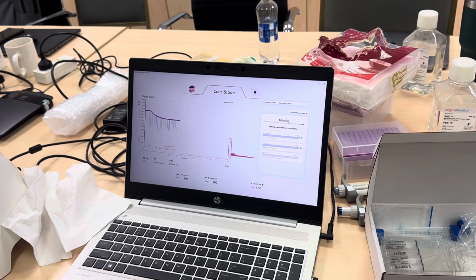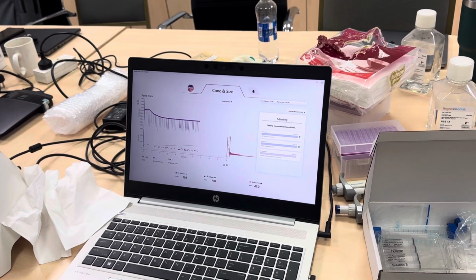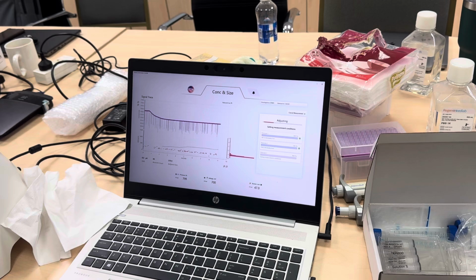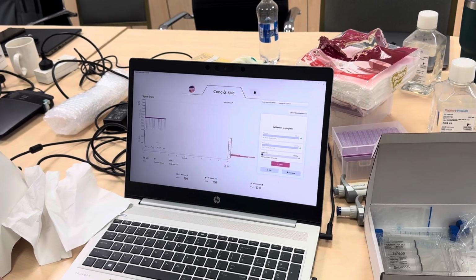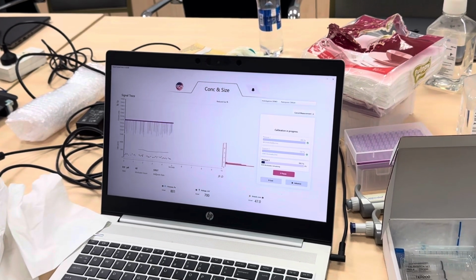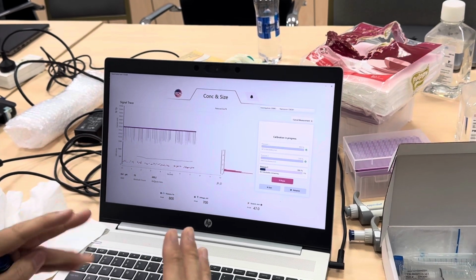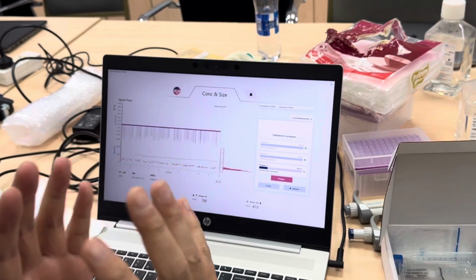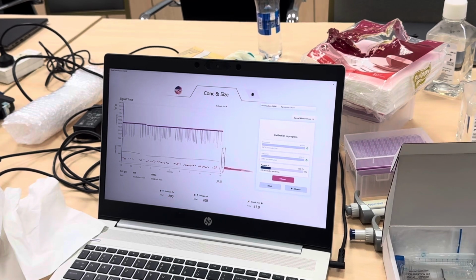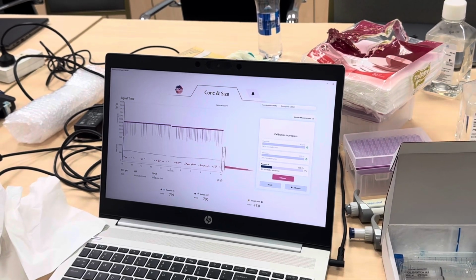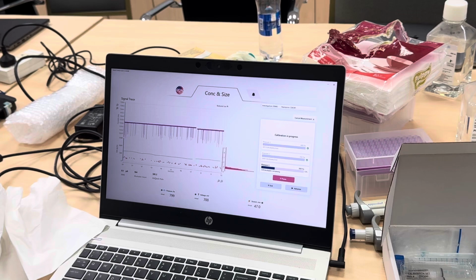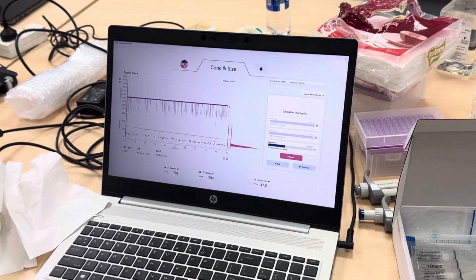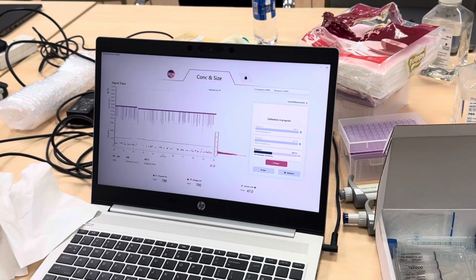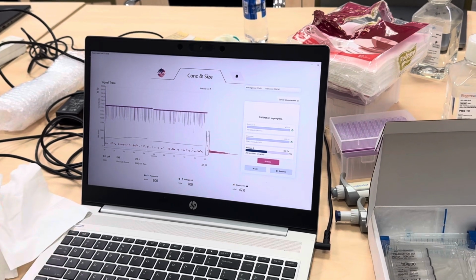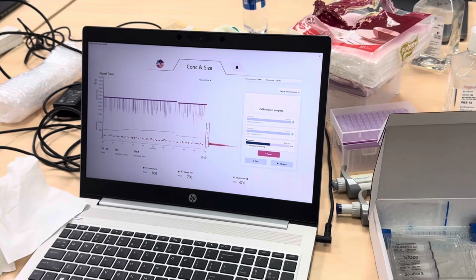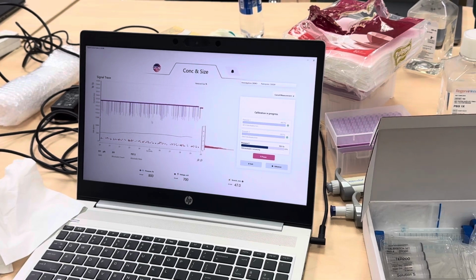Currently, you see that we didn't do any troubleshooting, but I need to say that troubleshooting is needed when there are very large particles, because you see the calibration particles are certified at a very narrow range, and sometimes for the UV, you cross from, for example, 50 to 400. So the nanopore size is a certain size, for example, around 400. So your large particles may block the nanopore. In that event, the baseline will drop a lot.